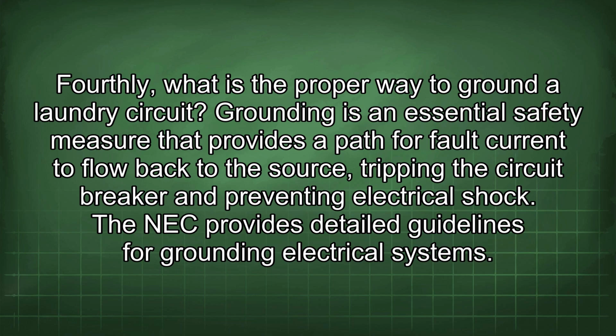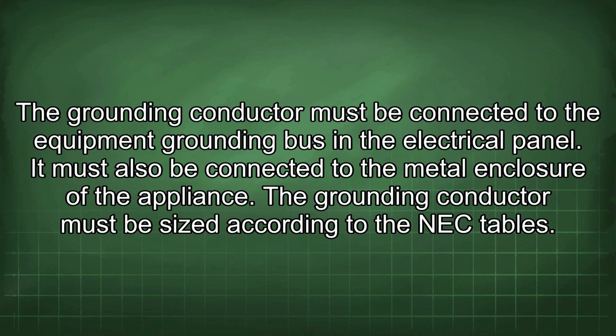Grounding is an essential safety measure that provides a path for fault current to flow back to the source, tripping the circuit breaker and preventing electrical shock. The NEC provides detailed guidelines for grounding electrical systems. The grounding conductor must be connected to the equipment grounding bus in the electrical panel. It must also be connected to the metal enclosure of the appliance. The grounding conductor must be sized according to the NEC tables.